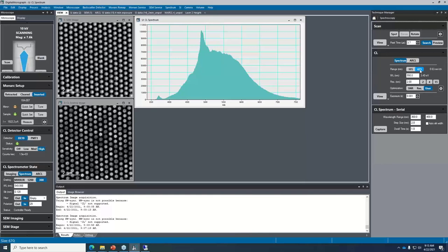There was a question: what is the spectrometer resolution? The spectral resolution depends on user settings: a larger slit reduces spectral resolution, and a higher dispersion grating improves spectral resolution at the cost of bandwidth. Right now there's 420 nm of bandwidth on the CCD. With the current setup I can achieve around one nanometer resolution — it might be 0.6 nm for this grating. Currently on a 300 grooves/mm grating; moving to a 1200 grating divides the bandwidth by four, bringing you down to around 0.12 nanometers.